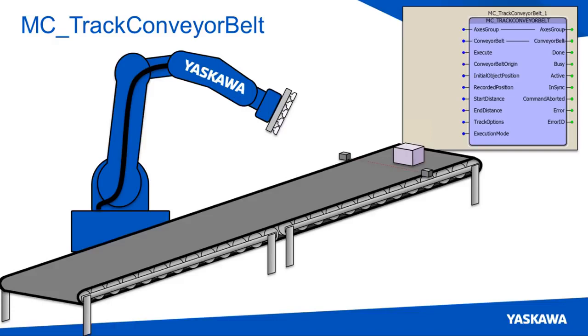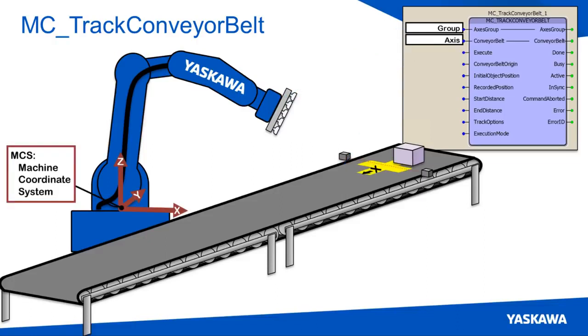The first thing I'm going to need to define in order to use this function block is what axis group I want to be part of this relationship, and what the axis is for the conveyor belt that's going to be part of this relationship. Next, I'm going to need to define the origin of the conveyor belt so that I can establish an offset between the robot and the conveyor belt. We call this the conveyor belt origin.